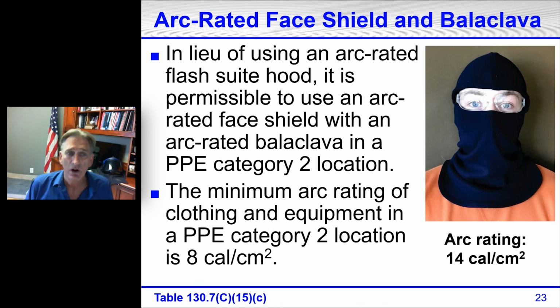All right, instead of using an arc rated arc flash suit hood, it is permissible to use an arc rated face shield with an arc rated balaclava in a Category 2 location. The minimum arc rating of clothing, remember in a Category 2 on that last slide, was 8 calories, or the slide before the last one. This is an arc rated balaclava. This has an arc rating of 14 calories per square centimeter.